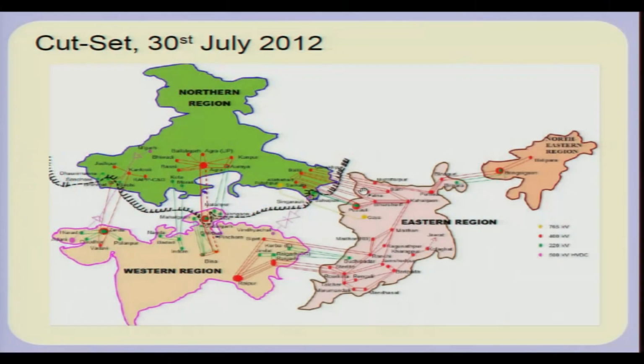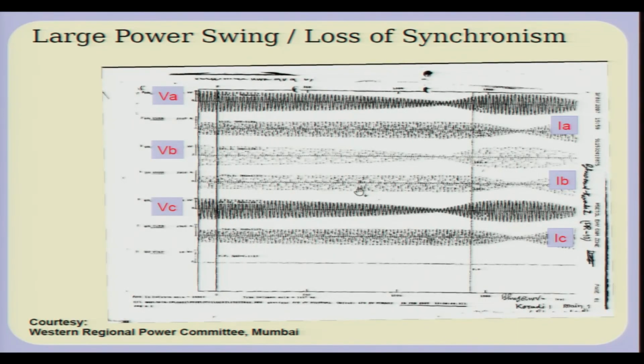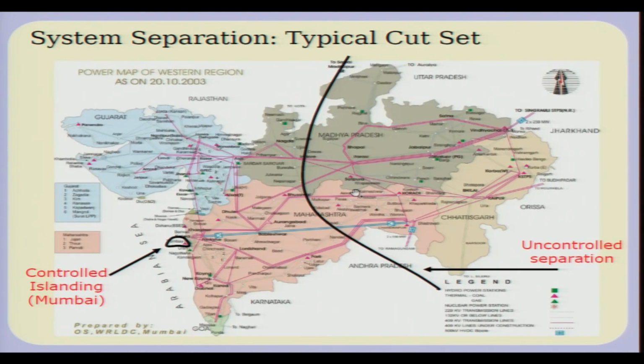Now, one important thing is that once you separate two systems, although initially the total load and the generation may be balanced, once the two systems separate out, the load and generation balance in individual synchronous grids changes. So, there are now two synchronous grids. In case the electrical connections between the two parts of the grid are broken, then you actually have two separate synchronous grids. And now within the two synchronous grids, you have to maintain load generation balance. Otherwise, the center of inertia frequency in each individual grid will not be stable. It will either fall down precipitously or increase.